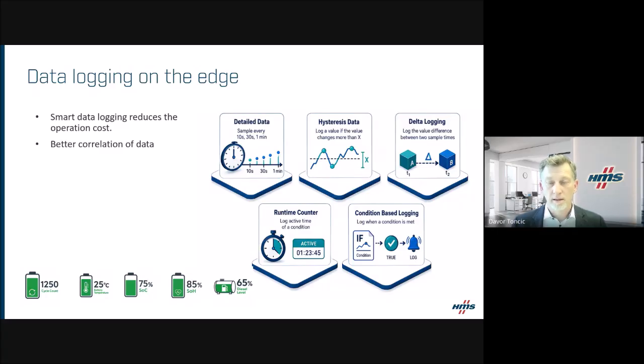So here we can put in some strategies in terms of how we're collecting the data, to reduce operation costs, because the more devices we have, we still need to consider those costs. Gateways could be configured to send data every minute or every 5 minutes, depending on the parameter type. You can also use hysteresis, where we only log data when it changes by a certain amount.